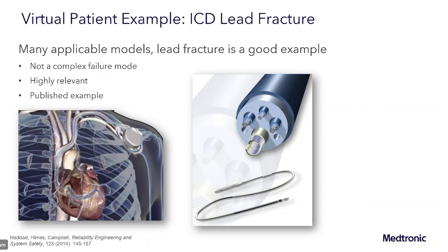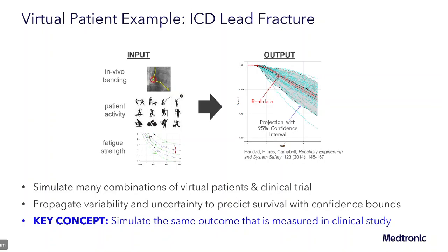All of these have flexible metal structures that have to resist fatigue. So there's a good body of evidence from other industries. Also, there are published examples. We had publications specific to this model already in the public domain. So it's a lot easier to collaborate with people outside your firm when you can work in a public space without having to get into confidential information.